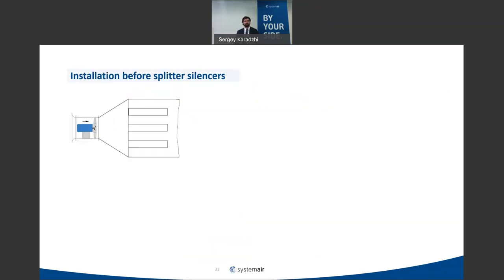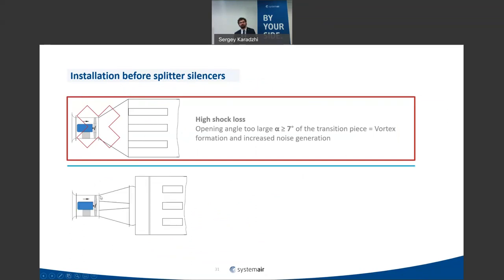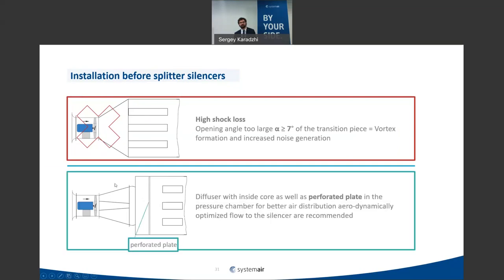Installation before a splitter silencer: if the opening angle before the silencer is greater than 7 degrees, you will have flow separation and high losses, and the sound direction will not be as expected. Always use small angles — less than 7 degrees — and a perforated plate to make the velocity profile more uniform.